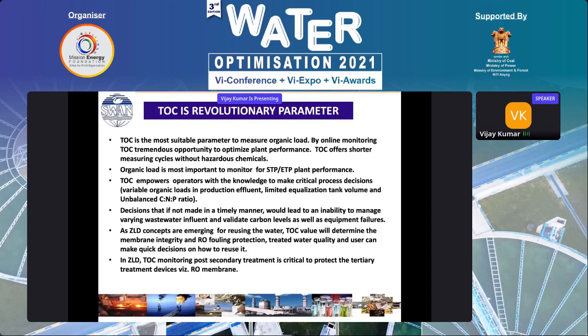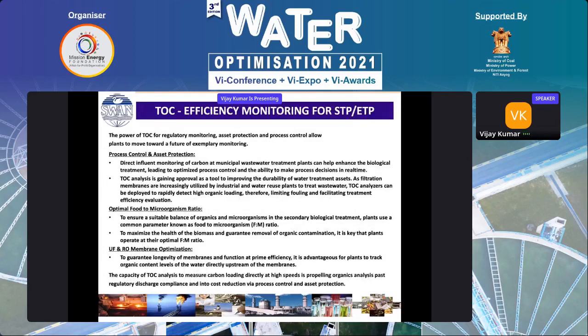With variable organic loads in production effluent, limited equalization tank volume, and unbalanced CNP, if decisions are not made in a timely manner, it would lead to inability to manage varying wastewater influent and validate carbon levels. ZLD concepts are emerging. For reusing water, TOC is valuable to determine membrane integrity and RO fouling, so the user can make a quick decision on treated water quality. The power of TOC is regulatory monitoring as well as asset protection and process control, allowing a move towards future exemplary monitoring. It guarantees the longevity of membranes functioning at primary efficiency.